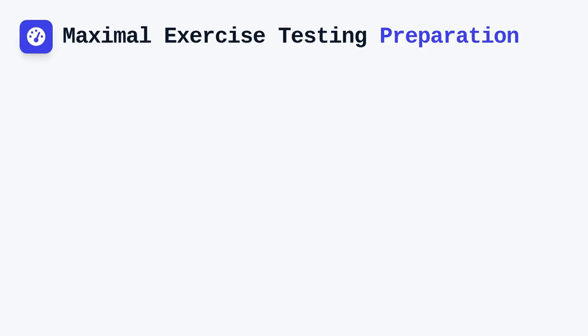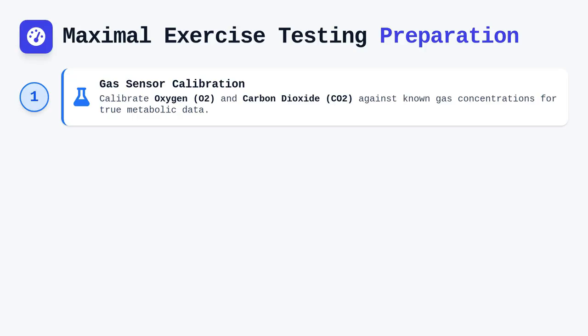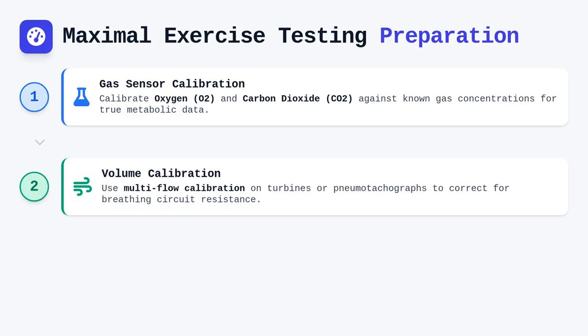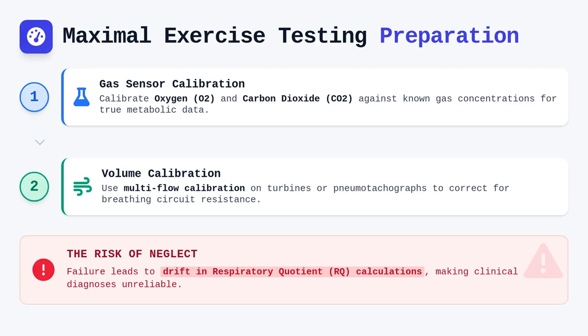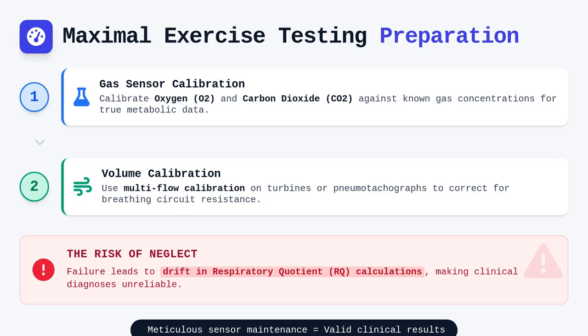Successfully executing maximal incremental exercise tests requires a disciplined approach to equipment preparation and physiological monitoring. Before a patient even steps onto the treadmill or cycle ergometer, we must ensure the metabolic cart is accurate through a rigorous calibration sequence. Oxygen and carbon dioxide sensors require precise calibration against known gas concentrations to ensure the breath-by-breath data reflects the patient's true metabolic state. Simultaneously, the volume turbine or pneumotachograph must undergo a multi-flow calibration to account for the resistance characteristics of the breathing circuit. Neglecting these calibration steps introduces drift into the respiratory quotient calculations, which renders the resulting ventilatory data unreliable for clinical diagnosis. High-quality data begins with the meticulous maintenance of these sensors, as precise volume and gas concentration measurements are the cornerstones of valid testing.